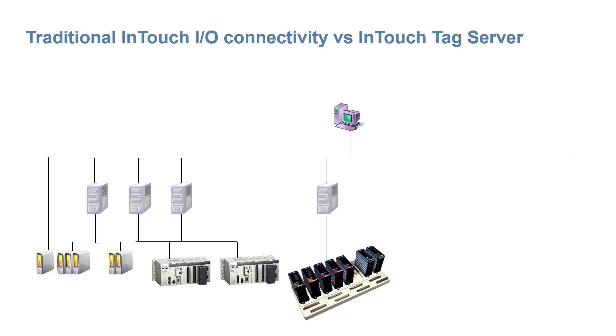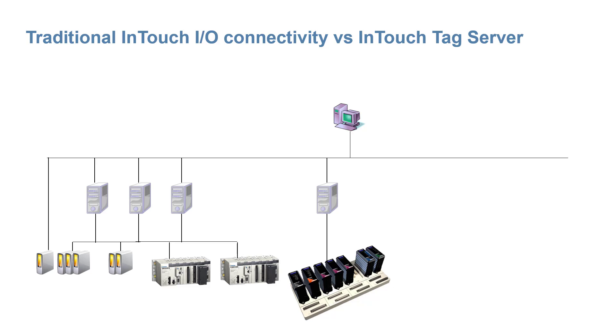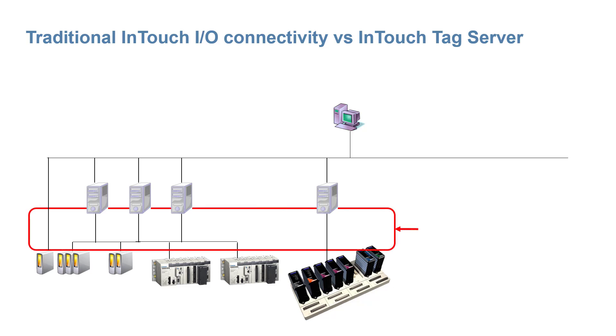Now let's compare traditional InTouch IO connectivity versus InTouch tag server. A typical factory network is usually separated into two parts: the plant network, which is usually high-speed Ethernet, and then the device communications on the plant floor, which may include older infrastructure sensitive to heavy traffic loads as it was never designed to support the additional bandwidth for SCADA or supervisory control and HMI.